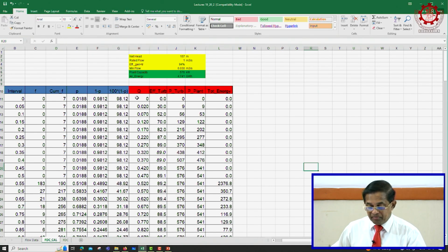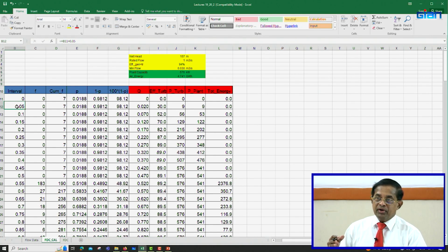So, I have put a column here as Q corresponding to our original line. Here I have put the value B12 minus J5. B12 is the corresponding flow rate, 0.05, minus the minimum flow, because at the diversion point we cannot use the full water coming in the river. We have to deduct the environmental flow. That is the only quantity we can use in the power plant. So, if we use the flow available there, that is wrong.